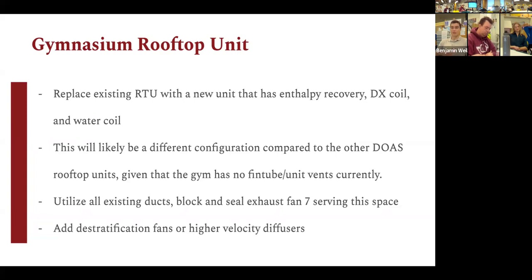So instead of running at 100% on, 100% off, you can run at quarter, 50%, which is better for energy saving. Our gym rooftop unit is a little bit different from the rest of the DOAS units because, as mentioned, that space is entirely heated and will be cooled by that rooftop unit. There's no hydronic system in there. So that unit will have to have a hot water coil that is sized for conditioning that space. And that hot water is going to be supplied by the air to water heat pump.